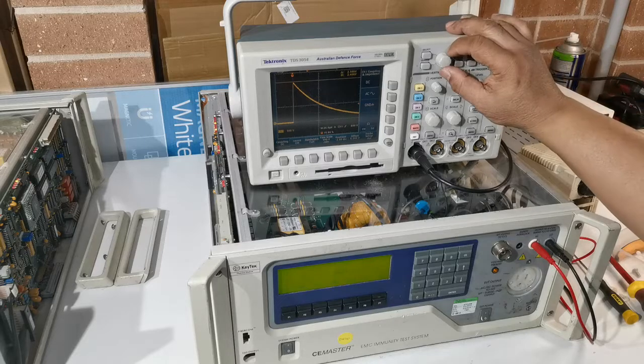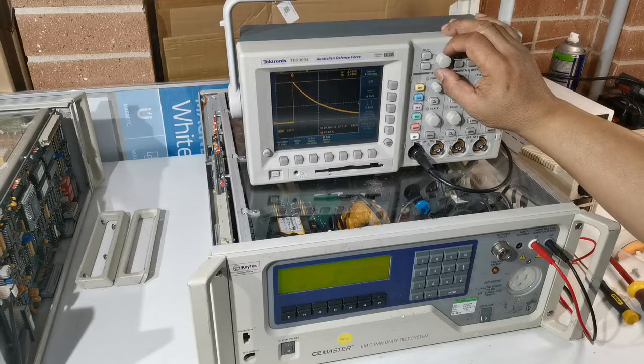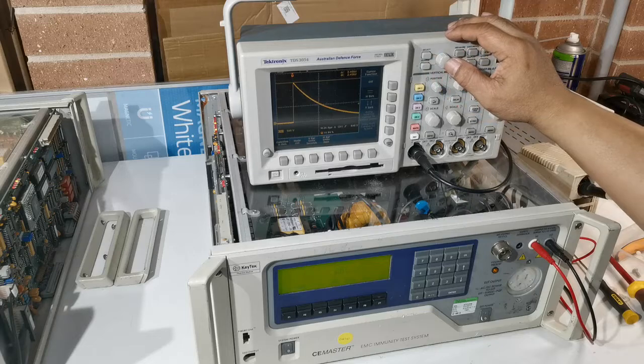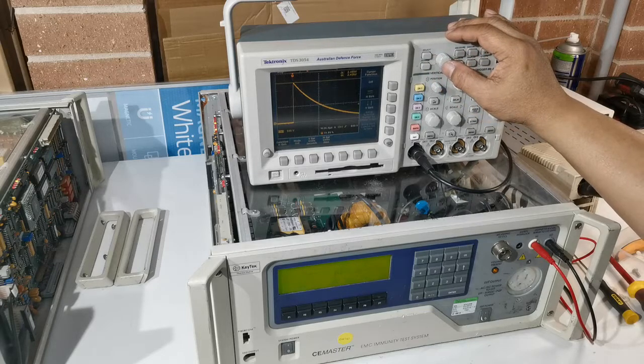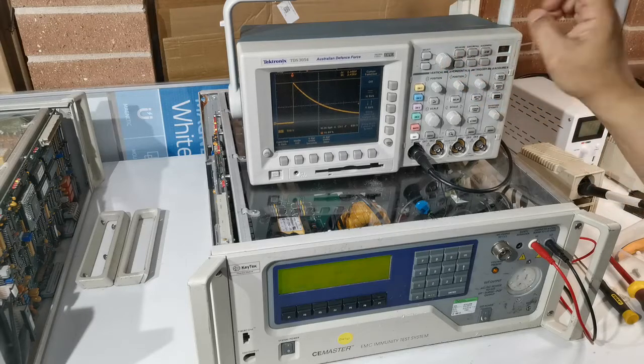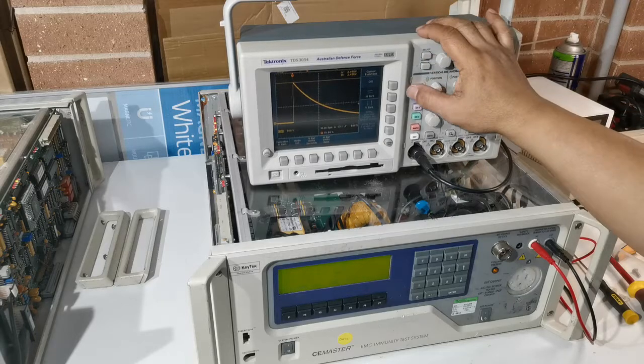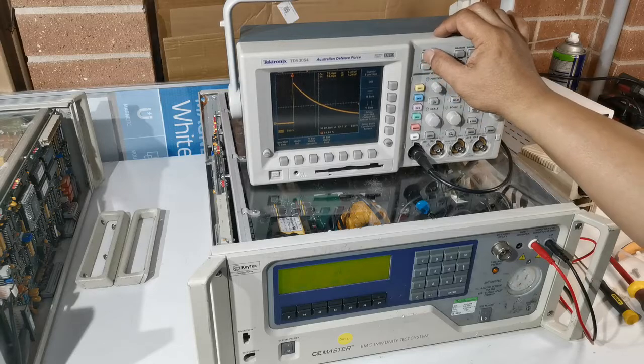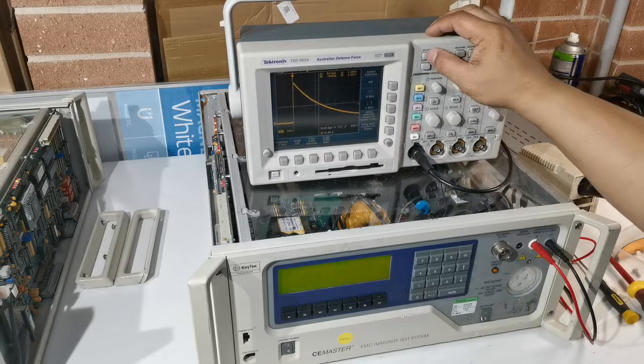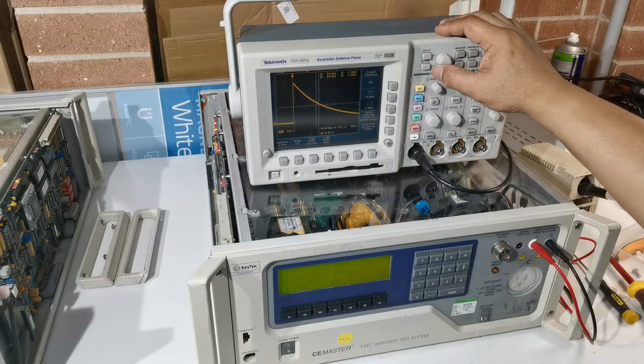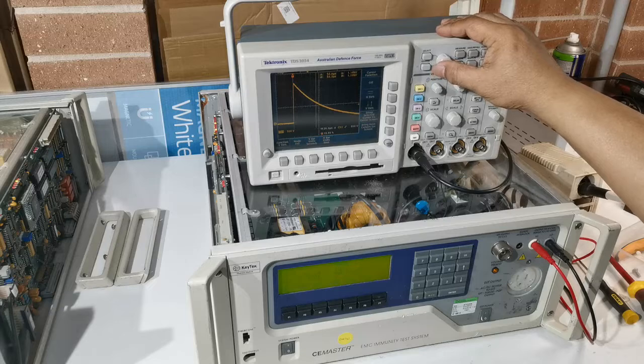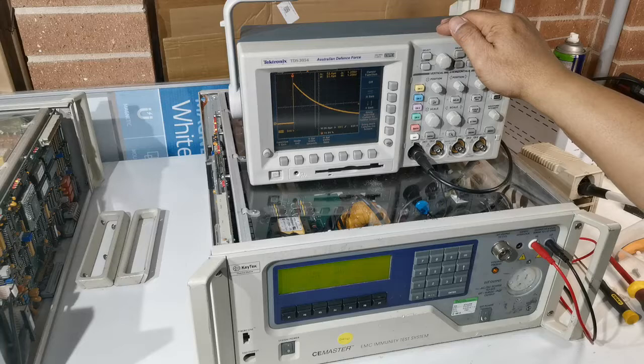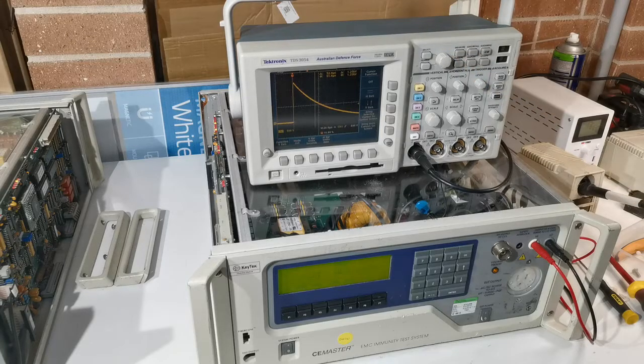Oh, that's perfect. So our peak waveform is 2.46, which is good. This is within 20% of the peak value, which is acceptable, as defined by the standard. So if we check the pulse width, I will stop that. Select. So pulse width is from, I think the new standard defines it from 10% to 50%. So 2.46, 2.5 is 1.25, around 1.25. So 52 microsecond, which is good.